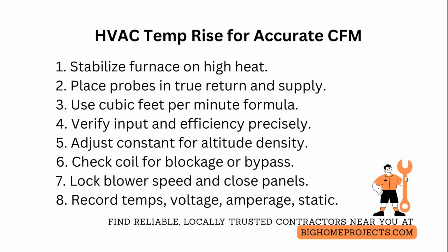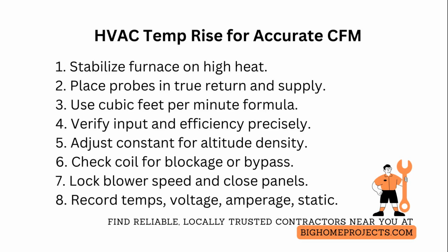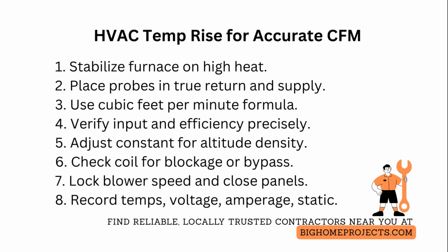First, stabilize the furnace on high heat for at least 10 minutes so the heat exchanger and supply air temperature fully settle, because transient readings make cubic feet per minute look higher or lower than reality.